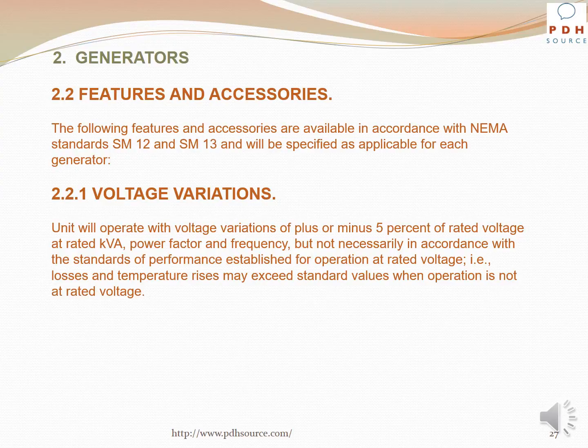Voltage variations: the unit will operate with voltage variations of plus or minus 5% of rated voltage at rated kVA, power factor, and frequency, but not necessarily in accordance with the standards of performance established for operation at rated voltage. That is, losses and temperature rises may exceed standard values when operation is not at rated voltage.